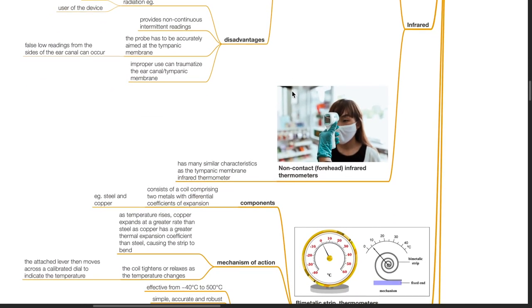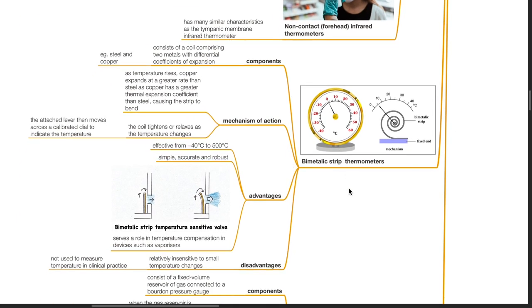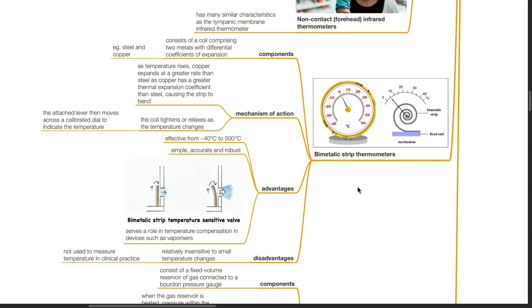Non-contact forehead infrared thermometers work on the same principles as the tympanic membrane infrared thermometer. Bimetallic strip thermometers consist of a coil comprising two metals with differential coefficients of expansion, such as steel and copper. As temperature rises, copper expands at a greater rate than steel — as copper has a greater thermal expansion coefficient — causing the strip to bend. The coil tightens or relaxes as the temperature changes, and the attached lever moves across a calibrated dial to indicate the temperature.